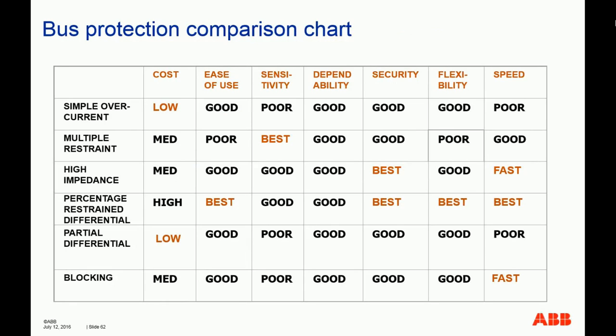Next, but not the last, is a comparison chart that illustrates the different types of bus protection schemes that I have covered in this presentation in terms of cost, ease of use, sensitivity, dependability, security, flexibility, and speed. You can look into this in more detail if you like, but in general, modern bus protection relay approaches have all basically migrated to the low impedance type of approach because of the less rigorous CT requirements, and also because that's the trend for modern numerical relay development and technology. Okay.